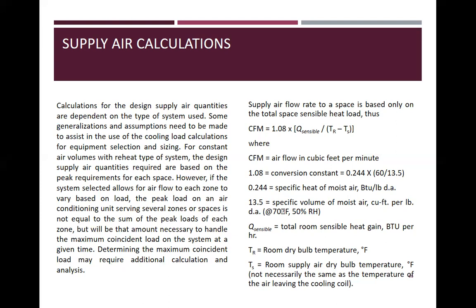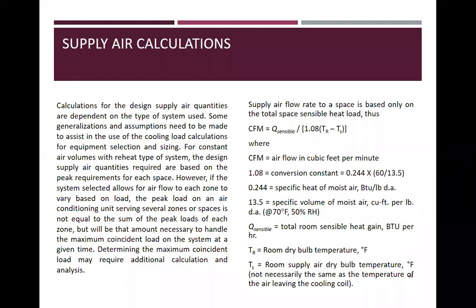Thus, CFM is 1.08 times Q sensible over T sub R minus T sub S. Okay, so CFM is equal to Q sensible over 1.08 times (T_R minus T_S), where CFM is equal to airflow in cubic feet per minute. 1.08 is a conversion constant, which is 0.244 times 60 over 13.5. 0.244 is the specific heat of moist air. 13.5 is the specific volume of moist air at 70 Fahrenheit and 50% RH.